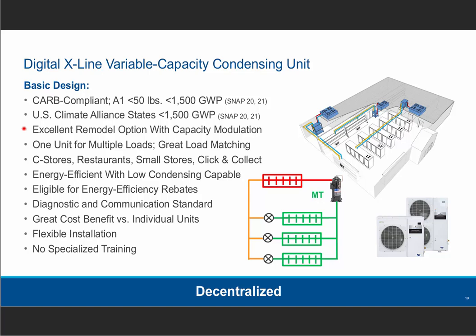Even for the remodels as well as new. It's got great load matching capabilities, and again, the application for small, medium, and click and collect type applications are nice. And click and collect, as you know, can have high variations in load, high heat load during the day with lots of opening and closing, managing that load, but at night the loads are low, they're not used, the unit's ability to scale down is there.